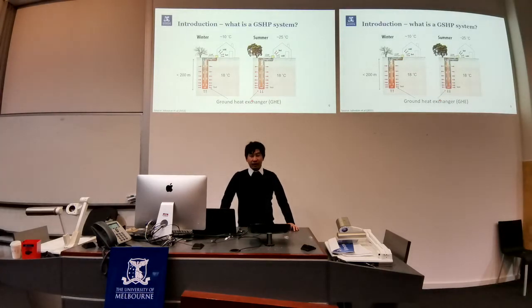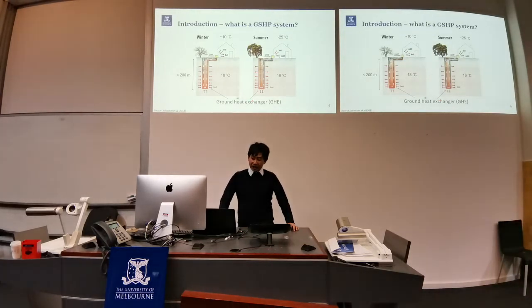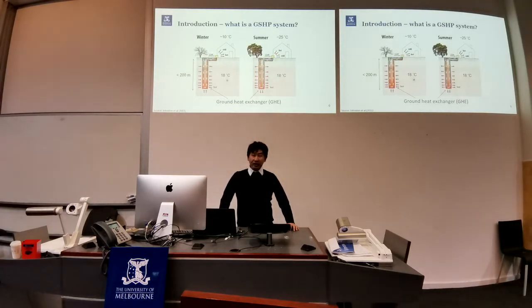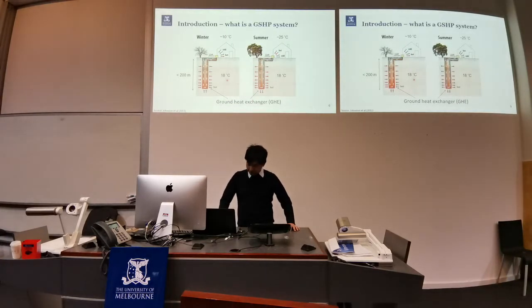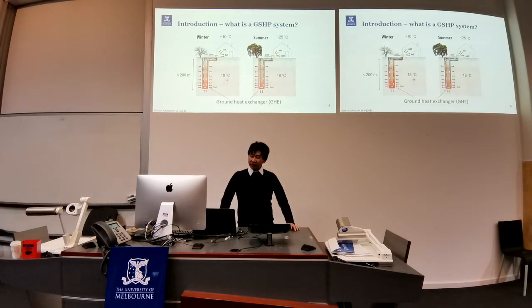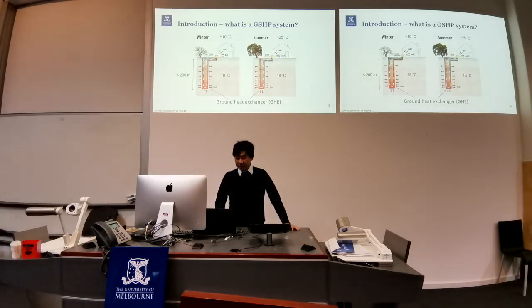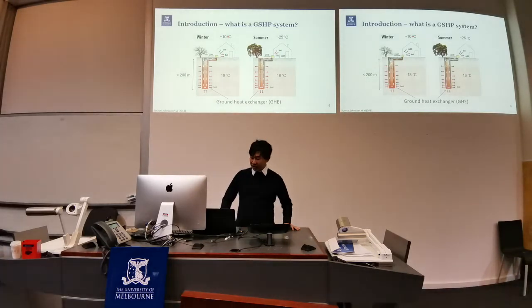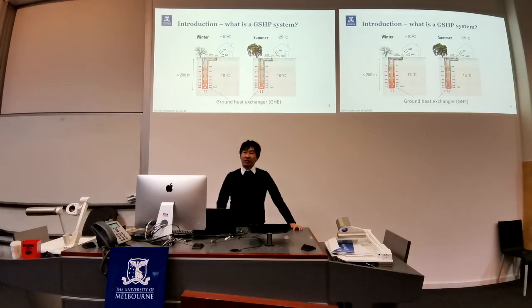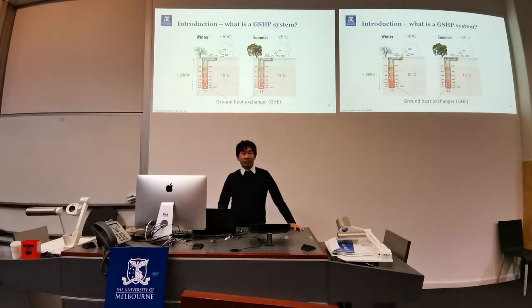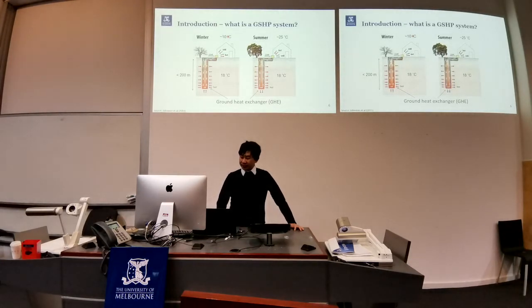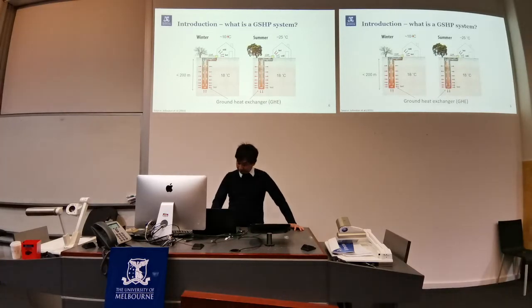The efficiency of this technology comes from the fact that the ground temperature is constant all year round. In Melbourne, this is around 18 degrees Celsius. As you can imagine, extracting heat from an 18 degree ground should be more efficient than extracting heat from about 10 degree air, just as a typical air condition works. Ground source heat pump efficiency has a coefficient of performance reported to be around 4. This means that 4 kilowatt hours of thermal energy can be provided to the building for 1 kilowatt hours of electricity required to run the heat pump.